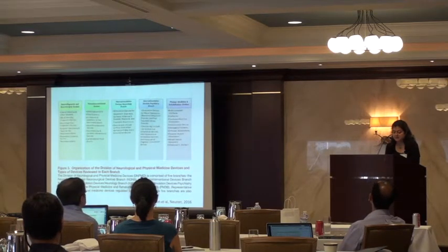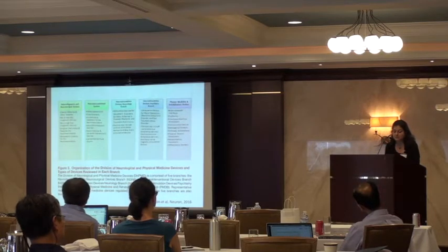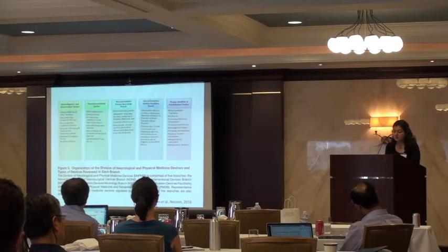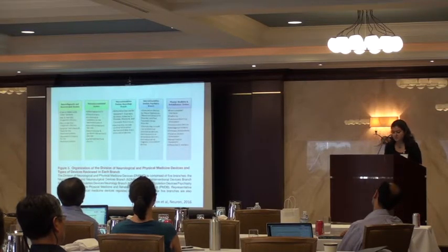So I found this really useful because when we were preparing slides for this, I came across this nice chart. There's a nice paper in Neuron talking through device regulatory pathways, and I recommend it if anyone is doing a device study because, like I said, it's more nuanced than a drug pathway from my perspective. But they're basically branches: the neurodiagnostic and neurosurgical devices, neurointerventional, neurostimulation, neurology, psychiatry, and PM&R. So I think it's helpful to see what kinds of devices are in this list, and so you'll have this slide as a reference if your device happens to fall in them, and then the contact person would be the person within that branch that you would want to reach out to.